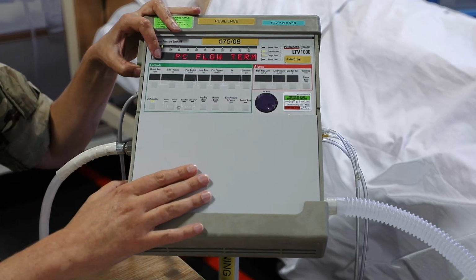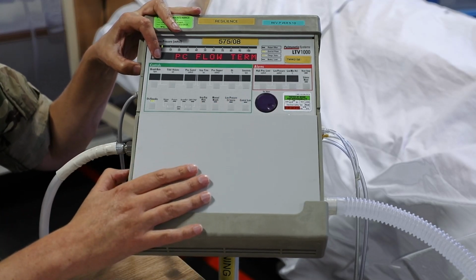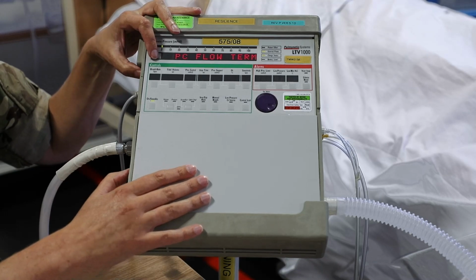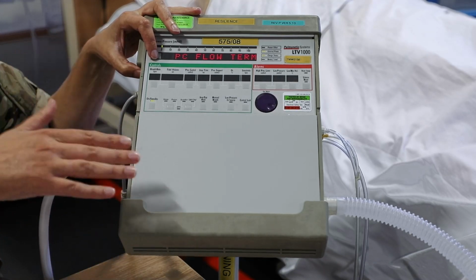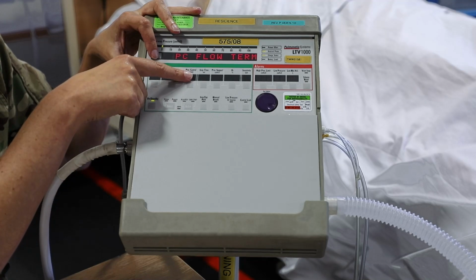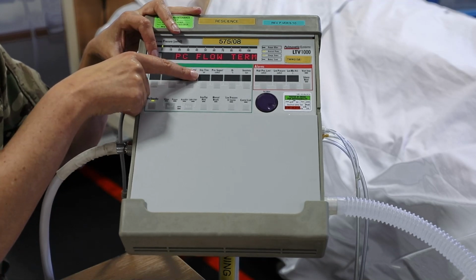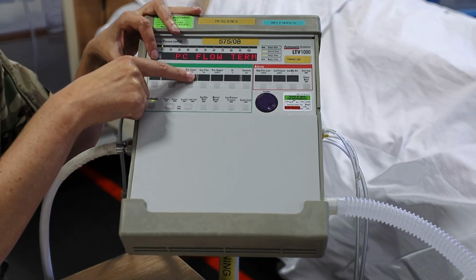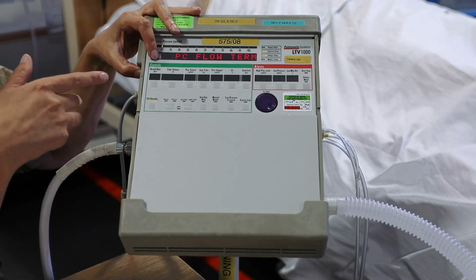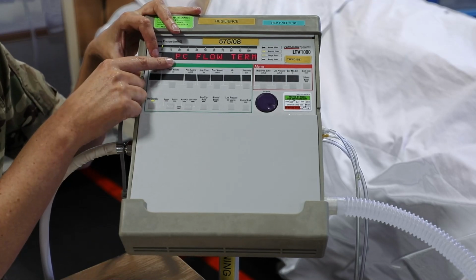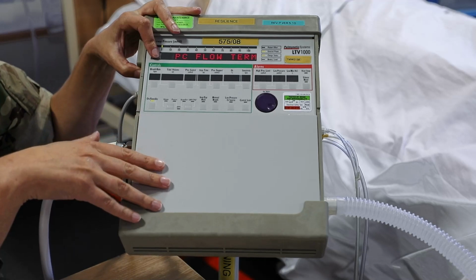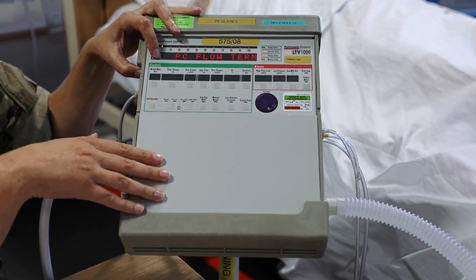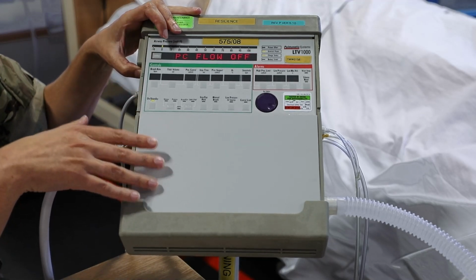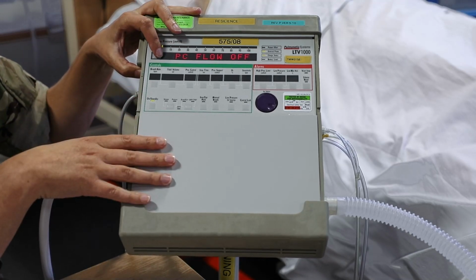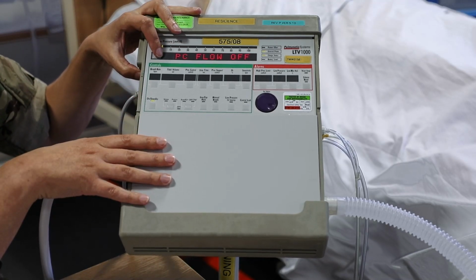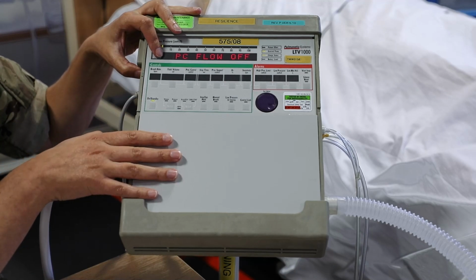Next is our pressure control flow termination, and this is just an alternative way of controlling our I to E effectively. On the LTV, we choose to control this using the inspired time, so we will set a time based on the respiratory rate that we require, but you can terminate those breaths into expiration using this termination option here.